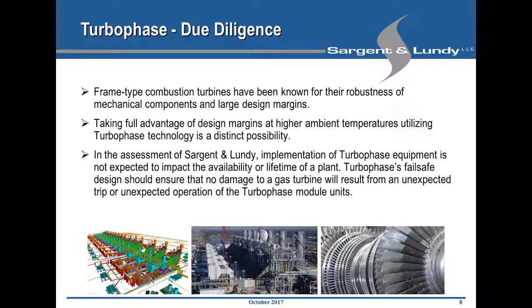Now, most of the interest when we are being contacted is from owners of frame-type combustion turbines. They are typically larger than 20, 25 megawatts, and the reason is that these units are very robust. There are thousands of those turbines out there. Many of them get older and have some deterioration. As those units get older, they might lose as much as 2, 3, 4, 5% of the power output. Therefore, owners and operators are looking at means of recovering that deterioration, and Turbophase is in that area of 10 megawatts, 20 megawatts that they can provide, depending on the size of the power station. As we said, it's about 10%. And clearly it is something that owners appreciate as an option.